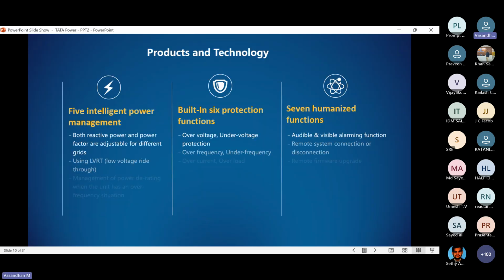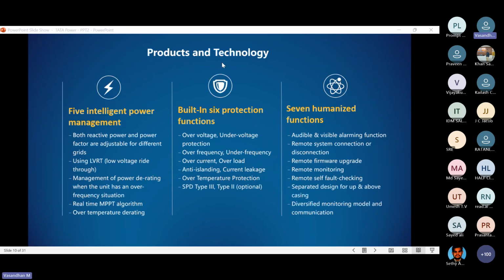So these are all product technology, how we can give the product technology for intelligent power management, both reactive power and power factor adjustable for different grids. We can give it through online mode also using LVRT, low voltage ride through, and HVRT also, and management of power derating. When the unit has an over frequency situation, that also we can manage. For example, derating, frequency derating.